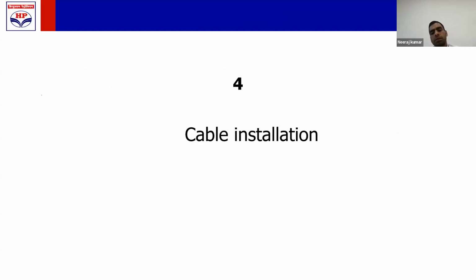And this completes the firefighting requirement or fire protection requirement for transformer installations. We have seen how the firefighting should be. Separating wall की बात करी. We talk about clear separation distance. We talk about fixed firefighting system. Then we talk about how to prevent oil from reaching the water stratum, in which we talk about oil containing pit and waste oil tank. This is how your fire prevention and control is done in the transformer.